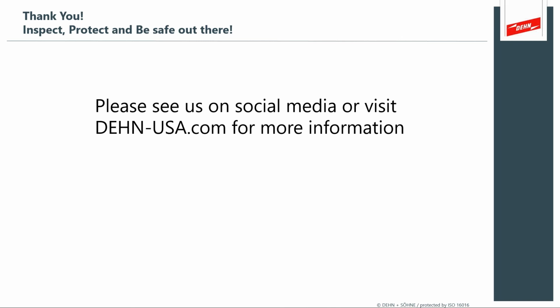That's really the best method I've encountered. Yes, and that just emphasizes the reason why you want to go for an SPD that has a visual indication to tell you if it's damaged or not. Some of them have a floating contact you can wire into a control system that tells you if it's been damaged. Or in the case of SPDs where you don't have a visual indication, you get SPDs with an internal RF communication module that you can put a tester on, and the tester will tell you the SPD's status. So there are different technologies out there that address how SPDs can indicate whether they're still within their useful life.